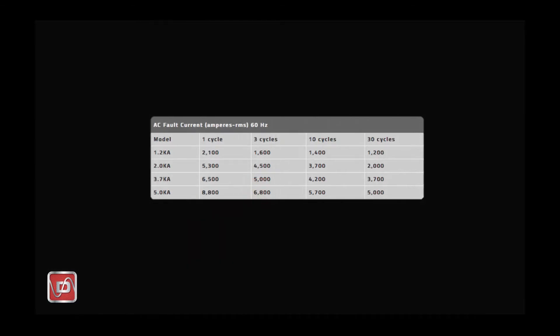You'll also notice that we often state AC fault current ratings along with the number of cycles it applies to. Cycles are merely a function of time, where 30 cycles equals one half second for 60 Hz power, and indicates the duration of time that the unit can withstand a fault at a given magnitude. One half second might not sound like very long, but in terms of an AC fault, it is significant. As 30 cycles represents the longest typical AC fault, and shorter durations are more common, you'll also see that we list several fault current ratings in a table arranged by duration, all for a single Dairyland device. Devices can handle higher currents for short time durations through a range of combinations down to lower current for longer times.